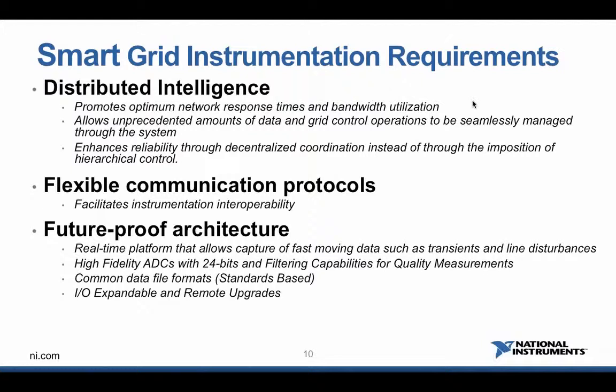First of all, a real-time platform. We want to capture fast-moving data such as transients and line disturbances. We also want measurement quality and the right granularity for the waveforms and disturbances we're capturing in the field. For that, we need high-fidelity analog-to-digital converters. We need common file formats to help with interoperability, such as ComTrade, for example. And we want to be expandable, as well as allow remote upgrades. We don't want to replace the asset in the field every time there's a need for a new feature or function.